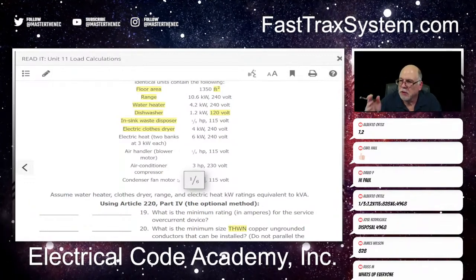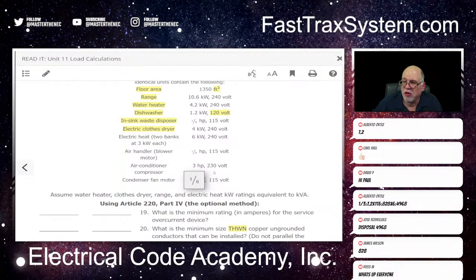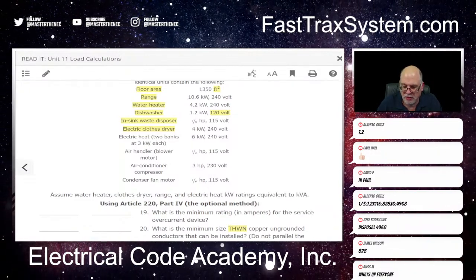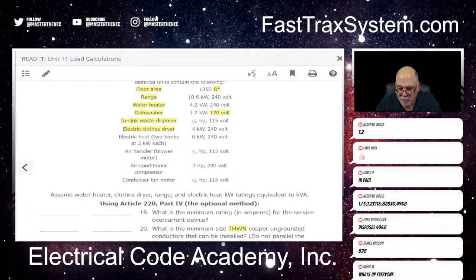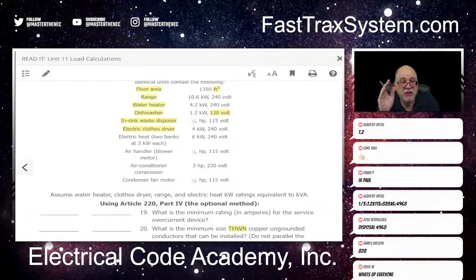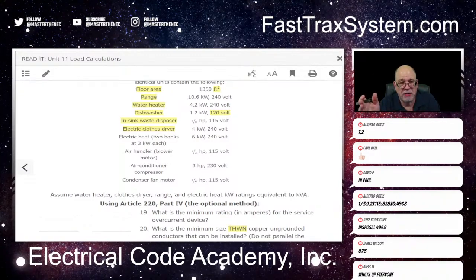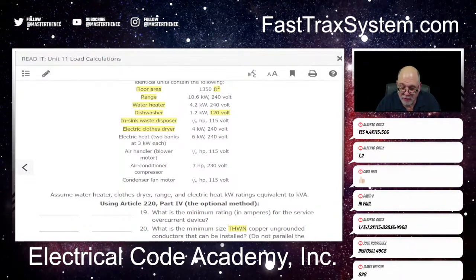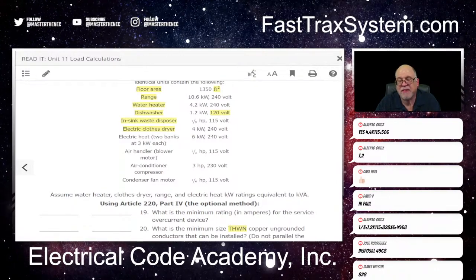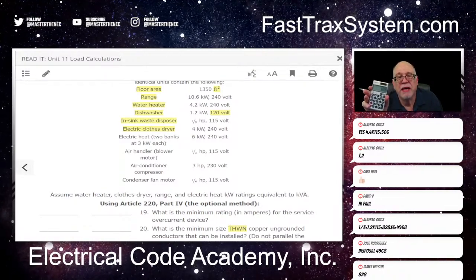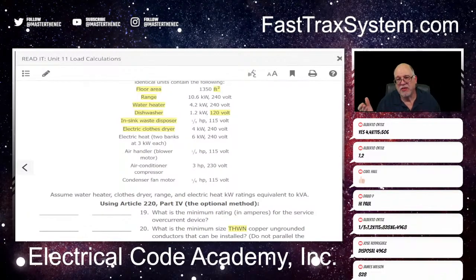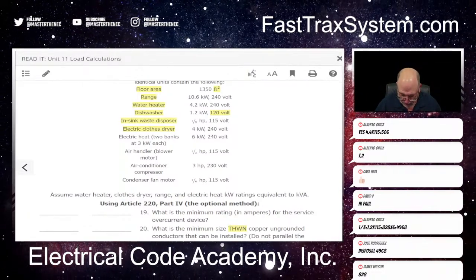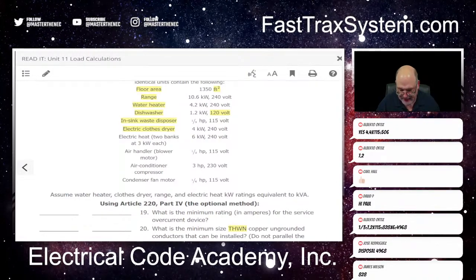All right, so let's start doing some calculations here. 6,000 is the heat, plus that 828 for that air handler, okay? So 6,000 plus 828 equals 6,828. So that's our heat with the actual blower contribution, okay? So that's that. Let me write that down.